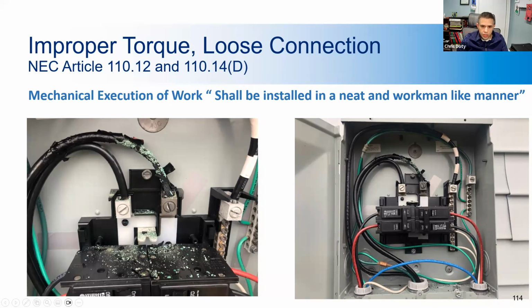So the only way to fix this was a complete replacement. We have no idea if the copper shards fell down into the panel behind the breakers, causing areas that could fail. So the only way to fix it was the contractor had to replace it all. That lug should have been torqued down to the value specified by the manufacturer. That's part of code. But that's an interesting situation. It's not likely you'll see it all that often, but it's obvious that there's something not right when you look at this panel. So keep an eye out for that stuff.